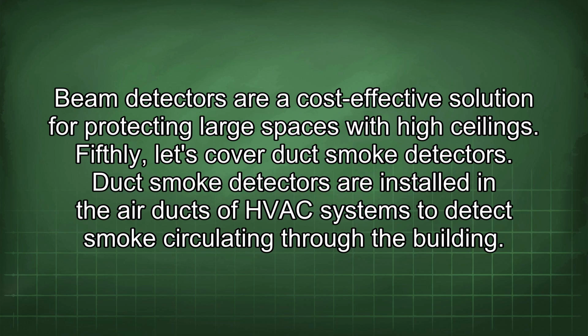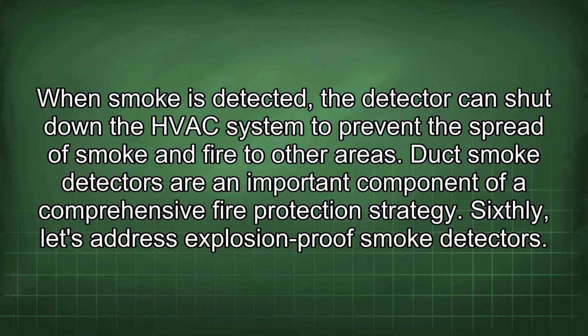Fifthly, let's cover duct smoke detectors. Duct smoke detectors are installed in the air ducts of HVAC systems to detect smoke circulating through the building. When smoke is detected, the detector can shut down the HVAC system to prevent the spread of smoke and fire to other areas. Duct smoke detectors are an important component of a comprehensive fire protection strategy.